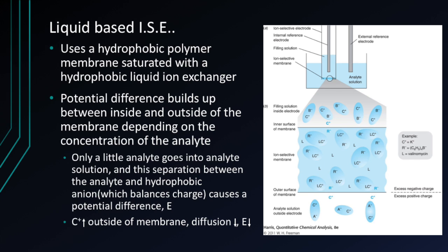The liquid-based ISE uses a hydrophobic polymer membrane saturated with a hydrophobic liquid ion exchanger. A potential difference builds up between the inside and outside of the membrane depending on the concentration of the analyte. Only a small amount of analyte diffuses into the membrane. The separation between the analyte and the hydrophobic anion, which balances the charge, causes a potential difference E. As the concentration of the analyte increases on the outside of the membrane, the amount of diffusion decreases, and as a result the electric potential also decreases.